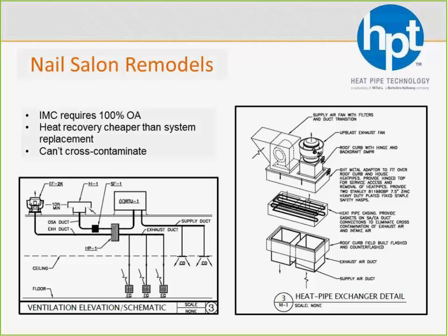So with the new IMC, if anybody has a remodel, whether it's HVAC related or not, that code inspector might come in and tell them that, well, hey, since you're remodeling, you've got to bring this up to code and make this 100% outside air. Well, one thing they can do is rip out the whole system and put in a nice new 100% outside air system. But my guess is they probably don't want to spend that money. So putting in a heat pipe, the heat recovery heat pipe, is a nice, less expensive way to meet code.